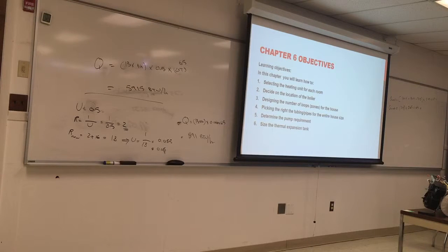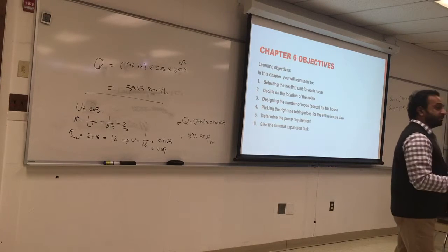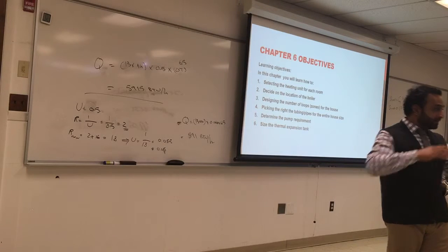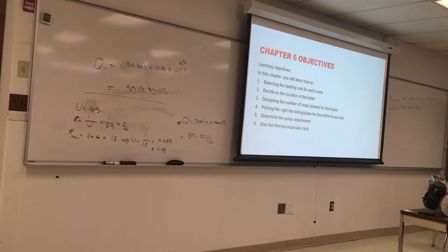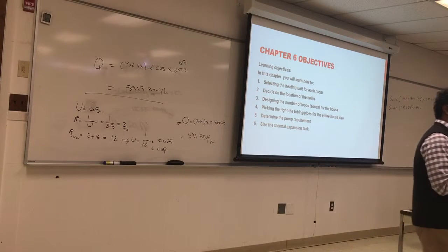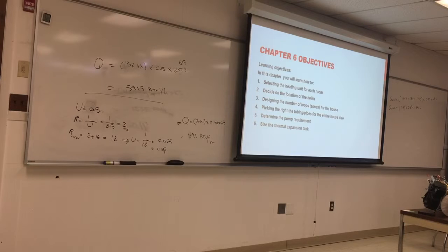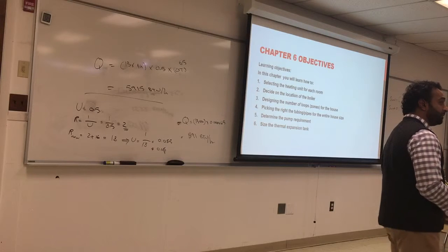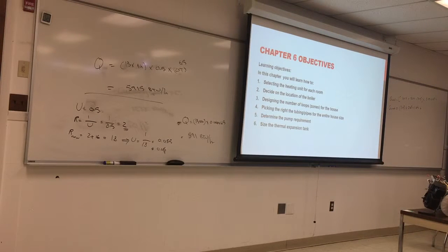Let's just think about it. Imagine we have a hydronic system. What is the water inside? It's a closed system, right? So the water should have a certain amount of gallons. So you have the water inside the boiler, correct? The water inside the pipes. The water inside the radiators. So what else? That's the entire water in the system. So you're going to calculate the entire amount and see what amount of expansion will happen when we heat the water from 65 to 180.